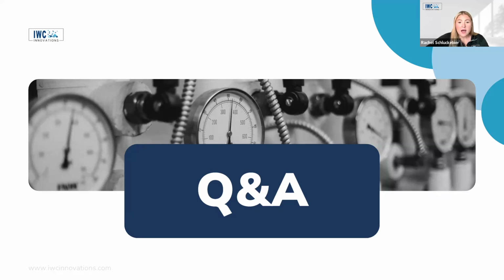We've got another question: how often should you change or clean aerators? Most of our water management plans, especially in the healthcare setting, default to quarterly for that control measure. Some facilities know they have hard water and there are reasons we might want to do it more frequently, or very soft water where there's not an issue and maybe we could back off and do that twice a year or annually, but quarterly is kind of the default recommendation. In some tricky, impractical jobs, we recommend maybe having two sets for the building, so whenever you're going around, you can swap in the new clean aerator and then clean the ones you just took off separately and have them ready for next time. It makes the job a little easier.